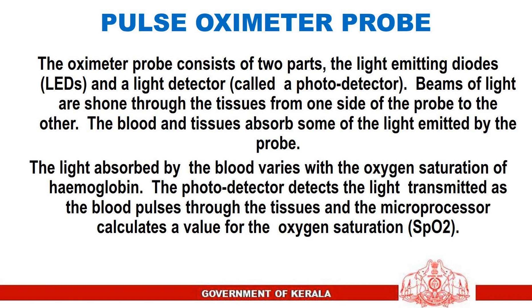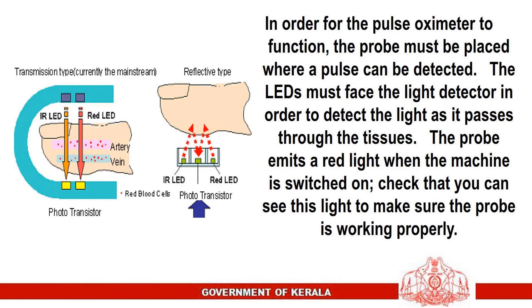Beams of light are shone through the tissues from one side of the probe to the other. The blood and tissues absorb some of the light emitted by the probe. The light absorbed by the blood varies with the oxygen saturation of hemoglobin. The photo detector detects the light transmitted as the blood pulses through the tissues, and the microprocessor calculates a value for oxygen saturation. In order for the pulse oximeter to function, the probe must be placed where a pulse can be detected. The LEDs must face the light detector to detect the light as it passes through the tissues. The probe emits a red light when the machine is switched on — check that you can see this light to make sure the probe is working properly.